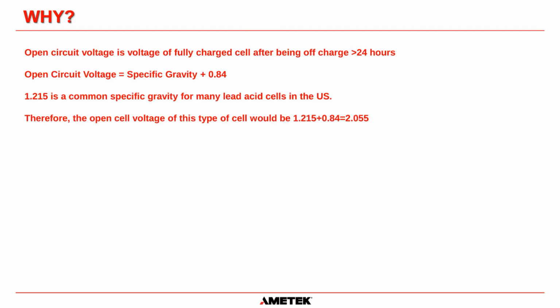For many lead acid cells, 1.215 is a common specific gravity. If you go to many of the data sheets for many of the lead acid cells in the US, the specific gravity of that cell may be 1.215. So the open cell voltage of that type of cell should be 1.215 plus 0.84, which is equal to 2.055. So very close to the 2 volts nominal that we discussed. We just wanted to prove to you that that's why we say a lead acid cell is a 2 volt nominal cell.